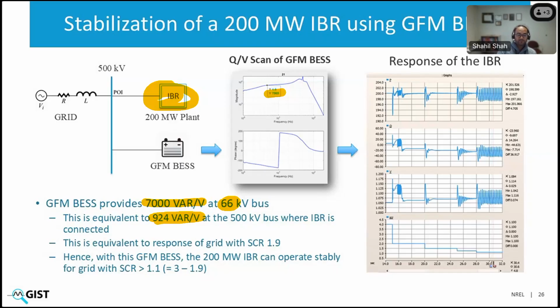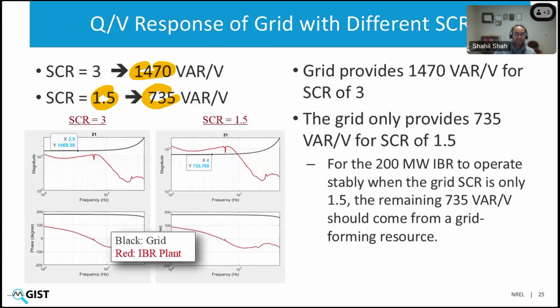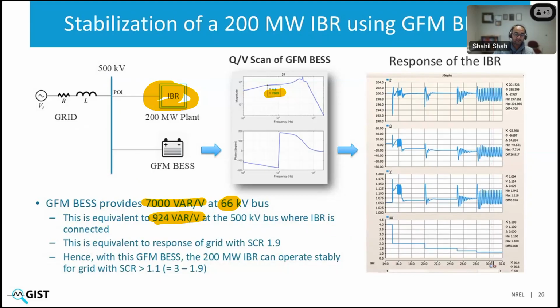We can actually go beyond that. We can get more information from this. So 924 var per volt. Let's see how much SCR, or grid short circuit ratio, it is providing. If I need 1470 var per volt of response for an SCR of 3, this translation from SCR to var per volt gain is done through a very simple equation, for both Q by V and P by theta. So if SCR of 3 corresponds to 1470 var per volt, it's a direct calculation that 924 var per volt is giving you grid strengthening of SCR of 1.9.